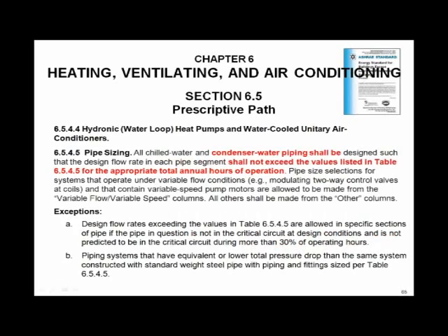design. Let's stay closer to condenser piping. Let's say specifically on that, and you'll see why I'm bringing this up to you now. There's another section here on pipe sizing in 90.1, and in red there, it clearly states condenser water piping. Clearly states it. Shall be sized per the values in table 6.5.4.5. So what am I telling you?